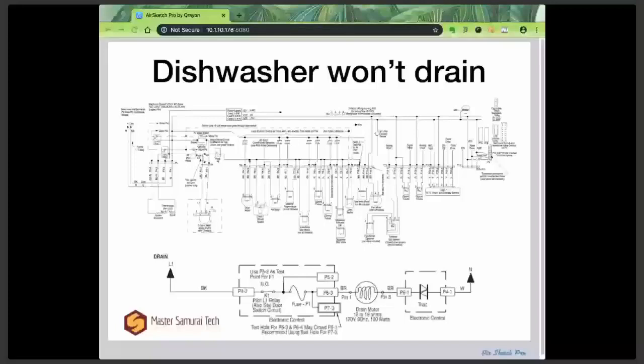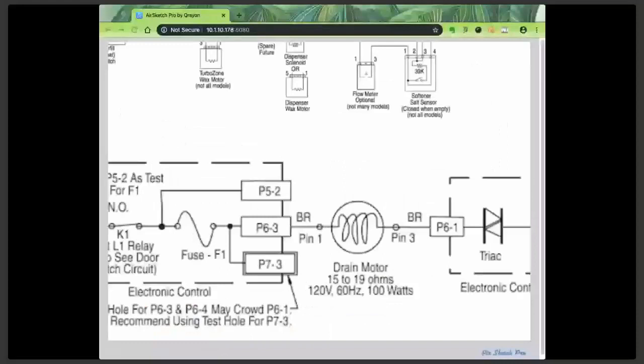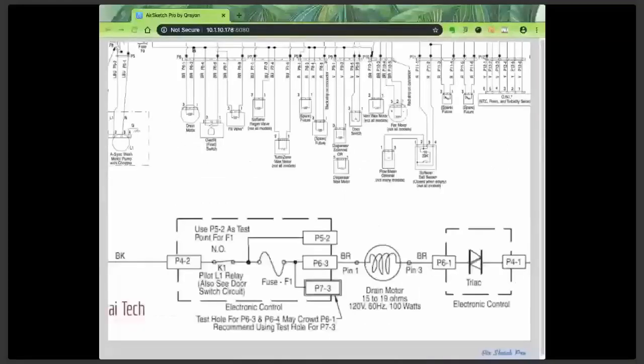Well, I've got a cut sheet down here, a line diagram for just the drain pump, drain motor right here. And they're telling me explicit specifications. They're telling me 120 volts. Blow that up a little bit. It's got a power supply of 120 volts. They're telling me the resistance of the windings, and they're giving me the wattage of that motor. All of those are explicit specifications. Not a fan of resistance, but if they give it to you, it might be a good idea to use it. It's something to check anyway.